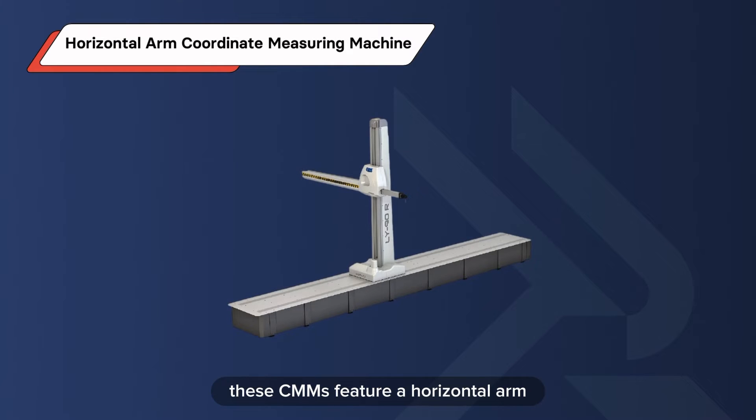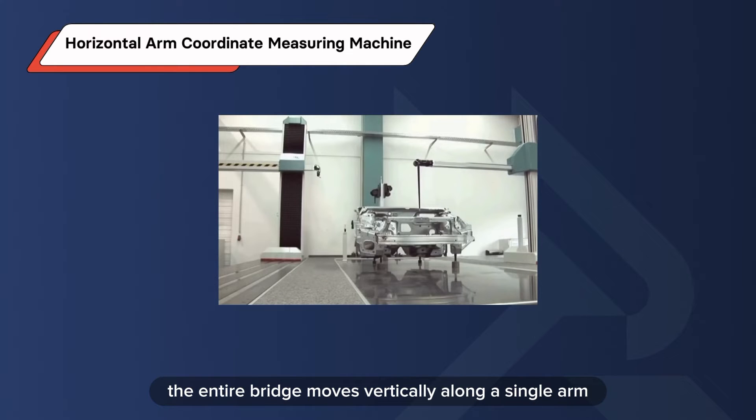Horizontal Arm Coordinate Measuring Machine. As the name implies, these CMMs feature a horizontal arm extending from a vertical column. Unlike the cantilever design, the entire bridge moves vertically along a single arm.